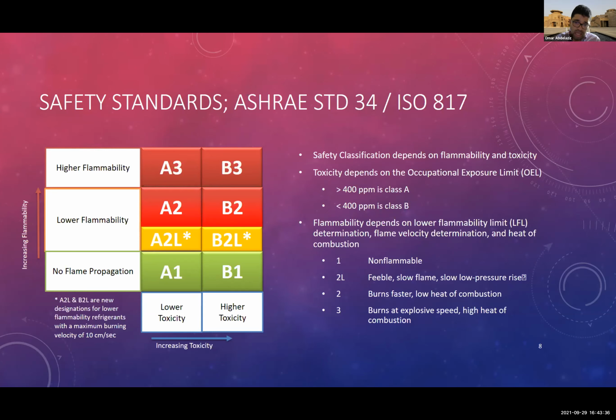Examples of class A include most of the HFCs like R134a, even CO2, HFOs, and all these refrigerants. Examples of class B include ammonia, for example. So ammonia at less than 400 ppm becomes a toxic environment. In terms of flammability, we start with 1 and move up. For 1, there is no flame propagation. That doesn't mean that it is not flammable. The refrigerant can be flammable, but it will not propagate the flame. So it is safe. We start with 1 and move all the way to 3.